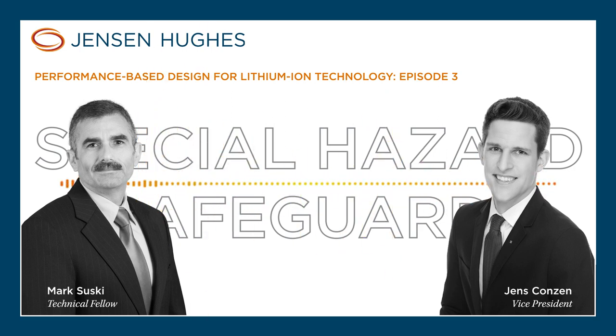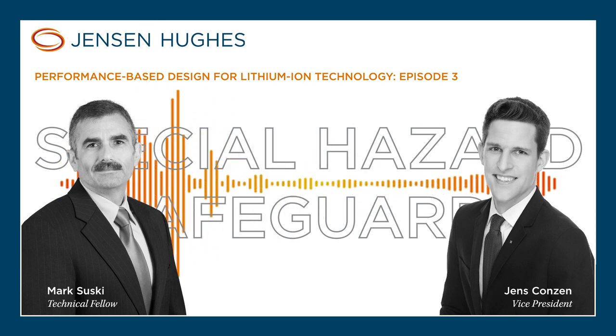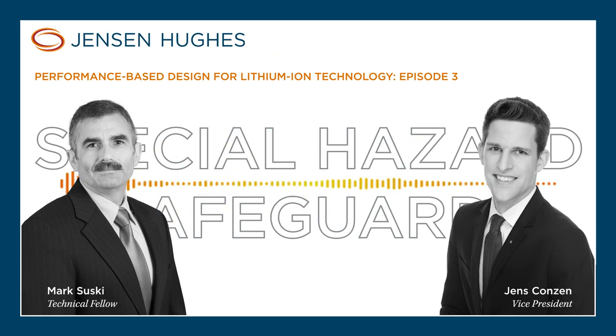Jens touched on it, so he talked about the risk hazard analysis, and I'm just going to touch on that a little further. That's probably one of the key items we think is necessary when working in these environments. That risk hazard analysis is going to set your game plan for the rest of the design. It sets the design criteria for the sprinkler system, for any sort of smoke detection systems, gas detection systems, any ventilation you may need, those kinds of things. Once that's in place, you're locked in, and you have your protection strategy specifically for your protected hazard.